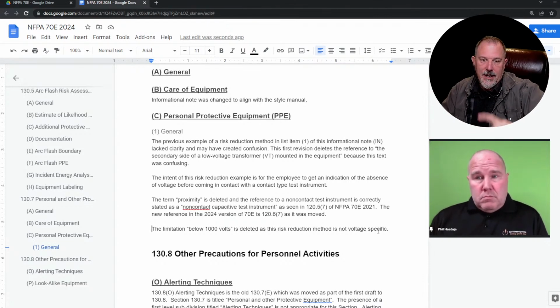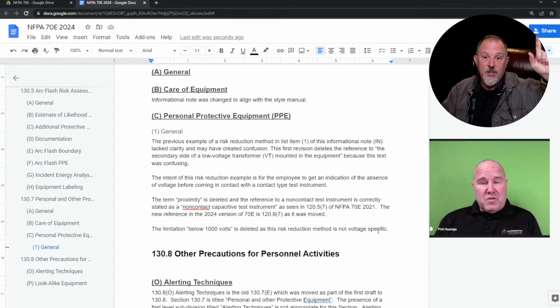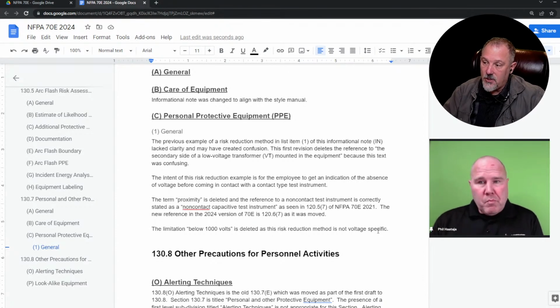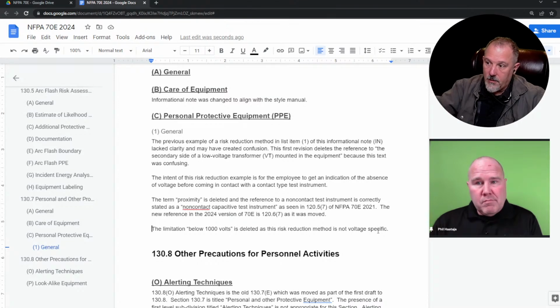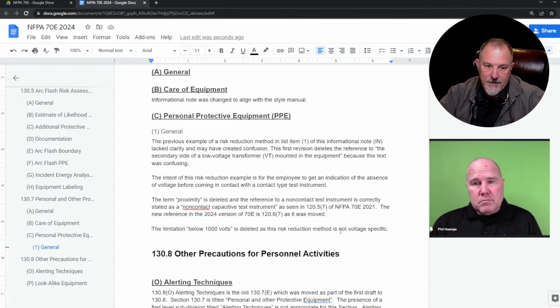Why is it high at the service entrance? Because your clearing time is based on the primary overcurrent device, which is that fuse on the utility side. So the energy at service entrance equipment can be very high, and there's no PPE rated for it. So they're giving you methods to say, look, you don't have PPE, but here are the steps you can take to reduce likelihood and severity.